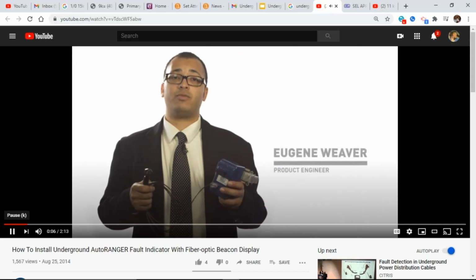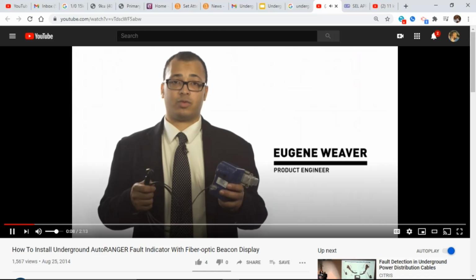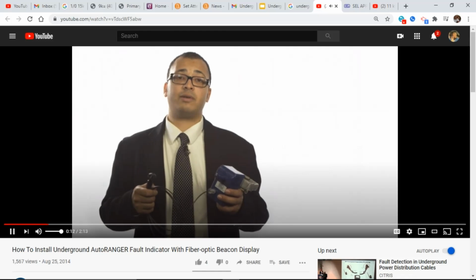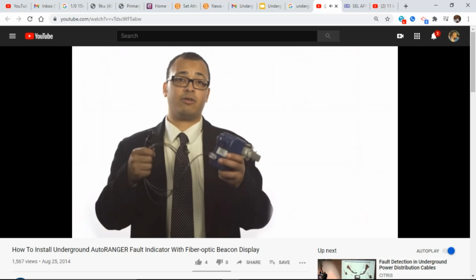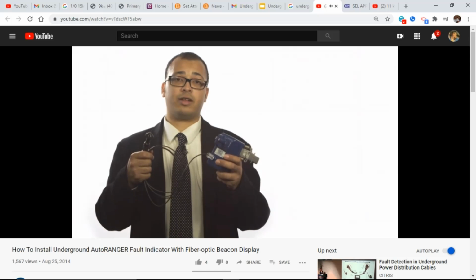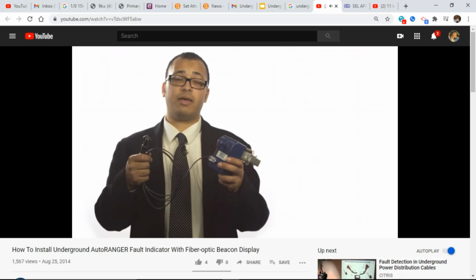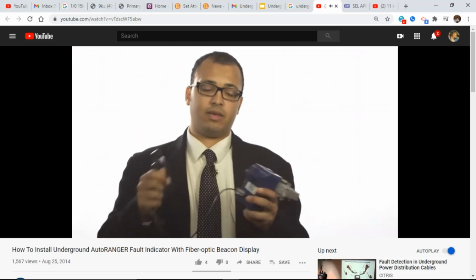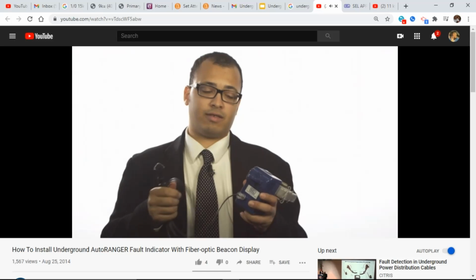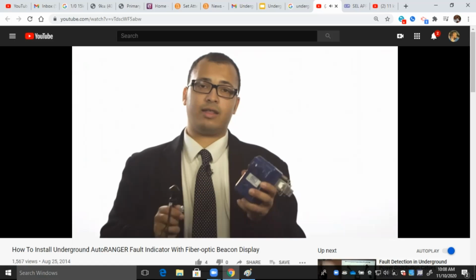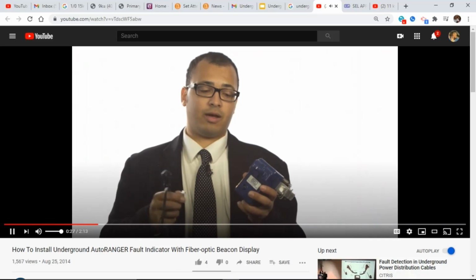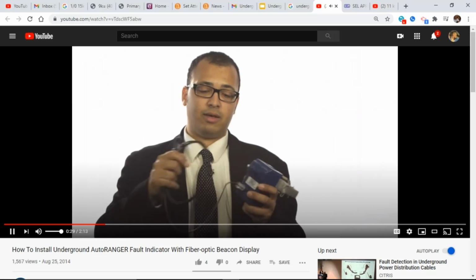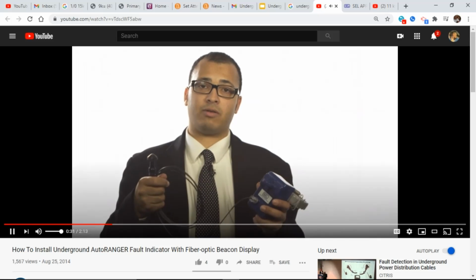Hello, my name is Eugene Weaver, and I'm a product engineer with Schweitzer Engineering Labs, Fault Indicator and Sensor Division. Today I'm going to show you how easy it is to install the Underground Auto Ranger faulted circuit indicator with fiber optic display on an underground cable. This phase sensor can be used as a single phase sensor with local LED indication, or it can be used with a remote fiber lead that mounts to the side of a pad mount enclosure.